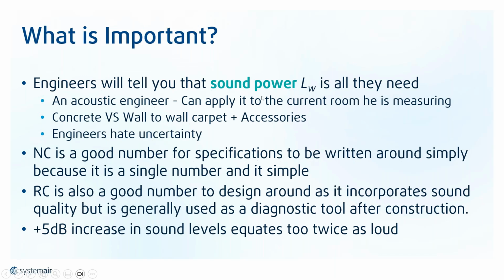Engineers will tell you that sound power is all you need, the raw sound power. You can gauge that classroom accordingly, and an acoustic engineer can apply it to the current room he is measuring. It changes if you have a classroom with concrete flooring, insulated acoustical panels on the roof, or fuzzy, shaggy carpet. All that changes the acoustics of the classroom. NC is a good number for specifications to be written around simply because it is a single number and simple. Another good thing to keep in mind is that approximately a 5 decibel increase in sound level equates to about twice as loud.